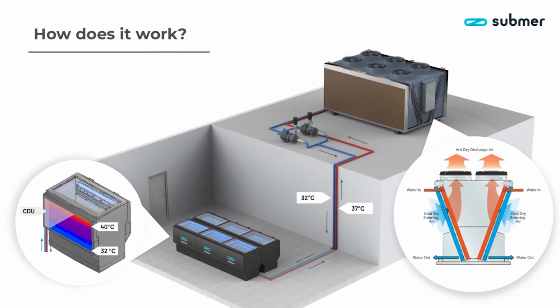How does immersion cooling work specifically? It's changing the medium, as I mentioned. Essentially, instead of air, we use a liquid which is non-conductive, capturing the heat from the IT equipment and transferring that heat to a water loop, which takes the energy outside of the building or allows for energy reuse.